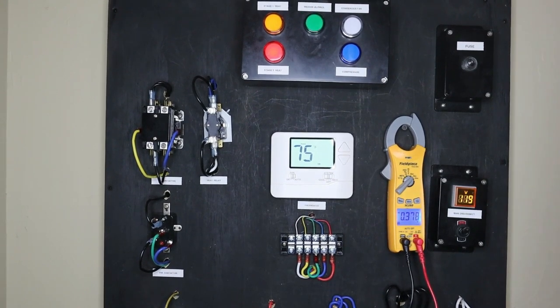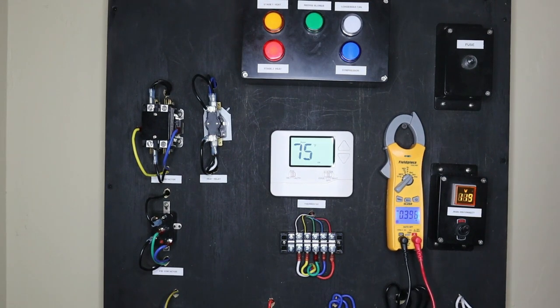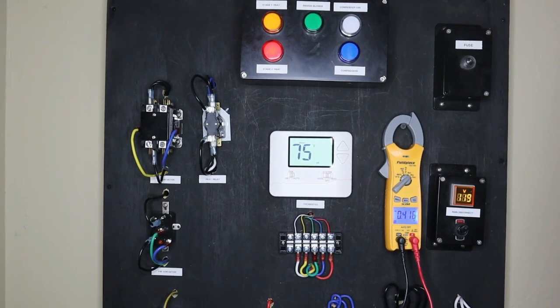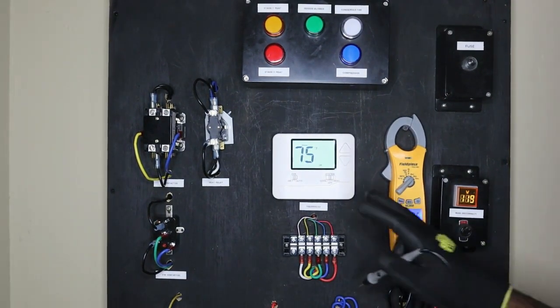Turn it off, now this relay it has an off-delay so after a few seconds you will see my stage one and stage two heat de-energize. Okay now they're both off.